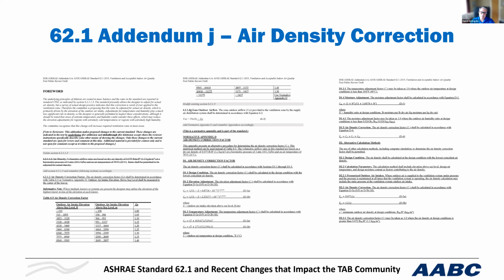So now switch a little bit and talk about density. This addendum is still in process, but it's very important, and it shouldn't be. It's actually been in the standard for a while, but this addendum, the way it's written, is trying to make it more explicit that there needs to be a ventilation rate correction. TAB personnel are used to making density corrections. Engineers typically have this done in automated load calculation software or selection software for a fan or other components. However, when it comes to ventilation, engineers typically aren't making the correction. Well, let's discuss why this is important.